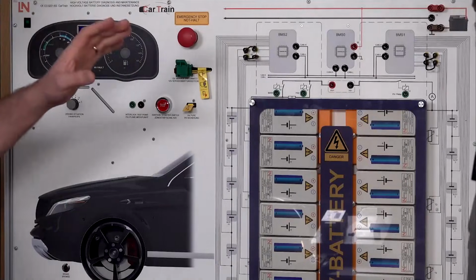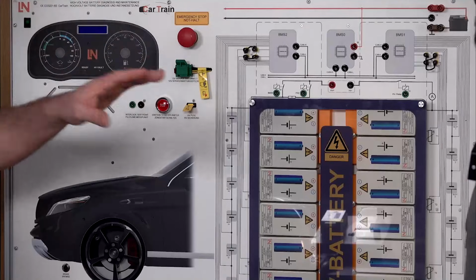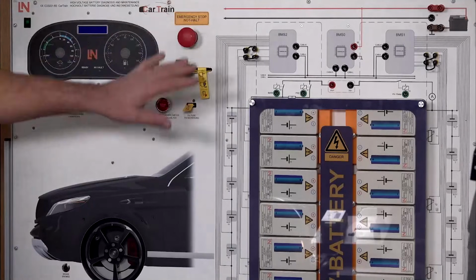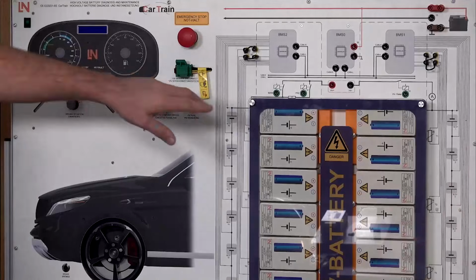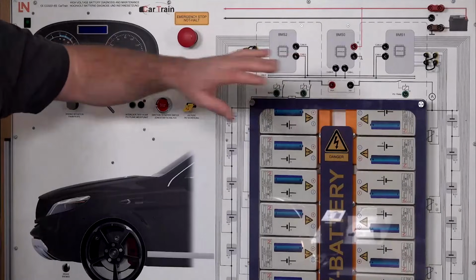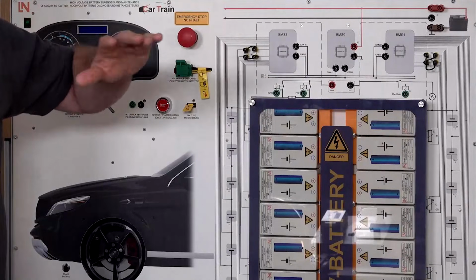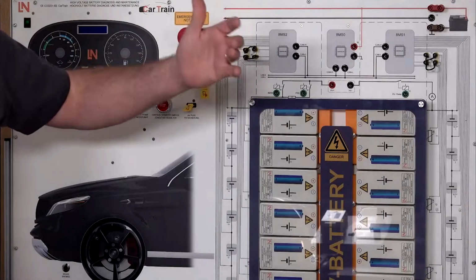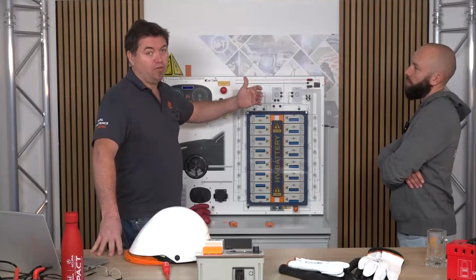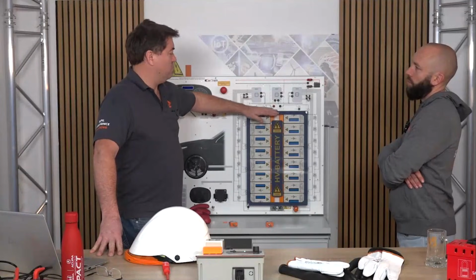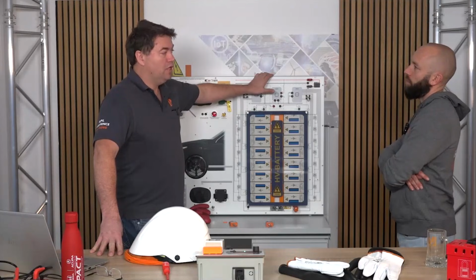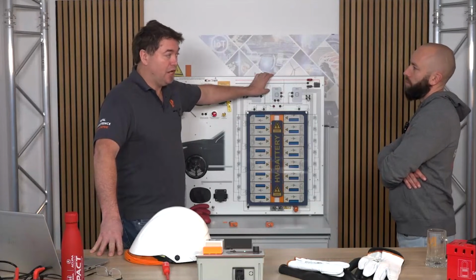Live-dead-live measurement is making sure the system is shut down and safe to work on, 100%. Because what can happen is the relays, if they're welded shut, which has happened, though not very often, you might be working on the system but it's not actually shut down.